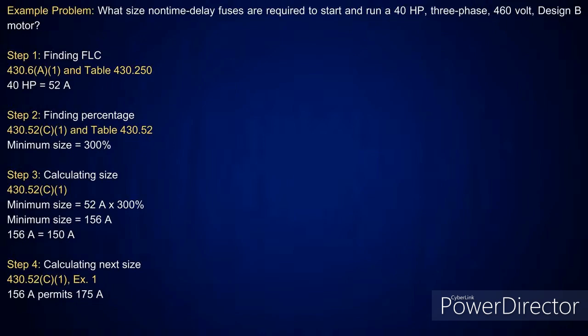Okay? Now, when we're doing this in our publications, we consider this a starting point as a minimum. If it'll allow you to go even smaller, you can go smaller, but this is a starting point. So we got a minimum started there, because after you get that point, then you can go to the next size, and then you can go to the maximum size. Now, as you look at the table, at the top of it, it's going to say maximum rating or setting. Now, let me explain this. I'm arguing with a bunch of those ECD boys, and I'm telling you, they don't know what they're talking about. But when you look at that, that is the maximum for the percentages in that table. You can't have two maximums.